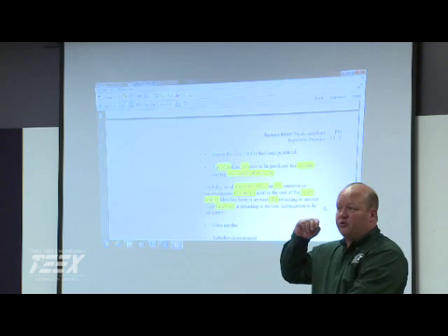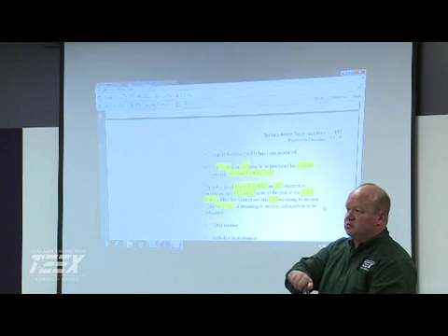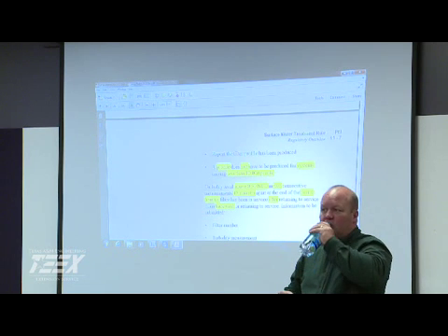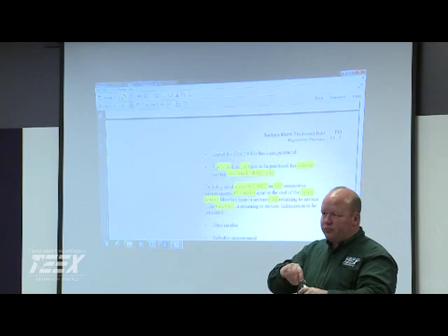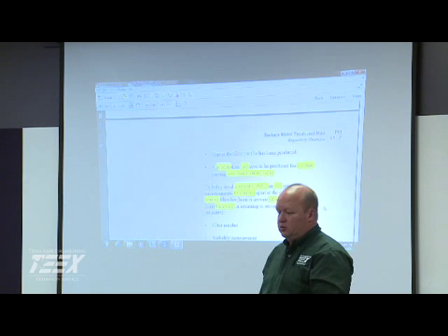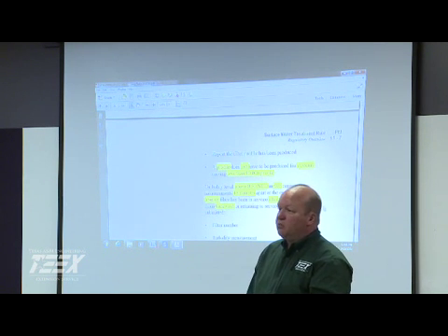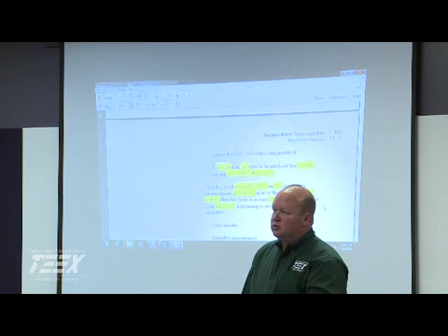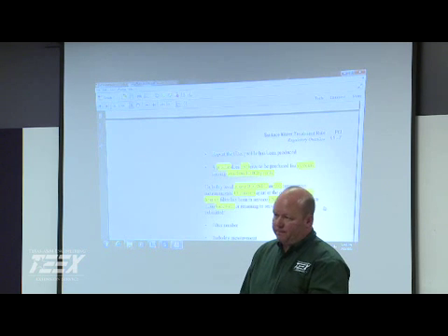Do y'all go out and help them do profiles on the small systems? Well, we've not seen a lot. Usually whenever there's a reading like that, there's an obvious reason for it. So they don't have to do a filter profile because they have an obvious reason, like mud balling, or the coagulant pump goes out and they didn't catch it in time.